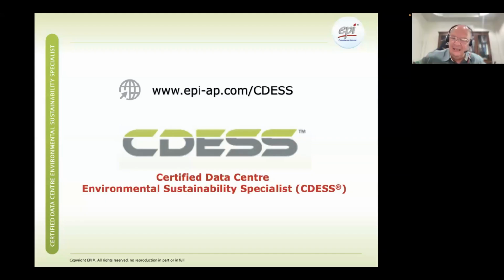Otto? Okay, that is actually a good question. Most countries have signed the Paris Agreement to reduce, or actually stop, global warming. And what we see is that this is translated into many different local regulations and requirements. About last year, a country like Singapore required a certain maximum PUE before you could even get a building permit to build a data center. So you need to design your data center already for a certain energy efficiency or sustainability performance.